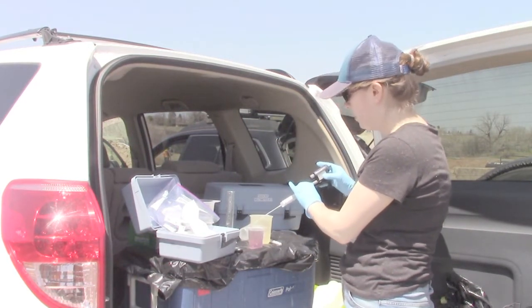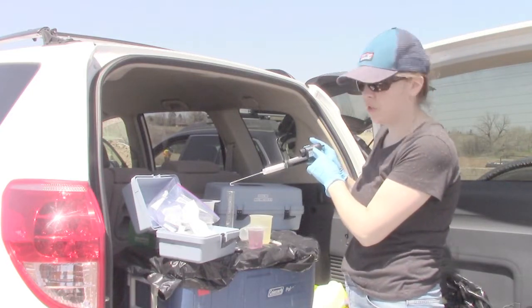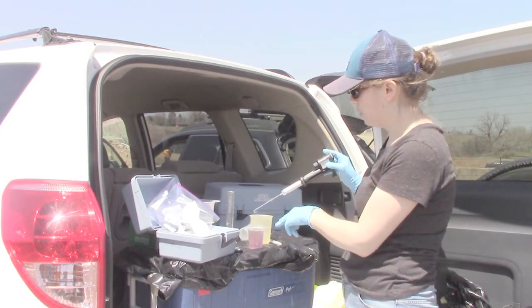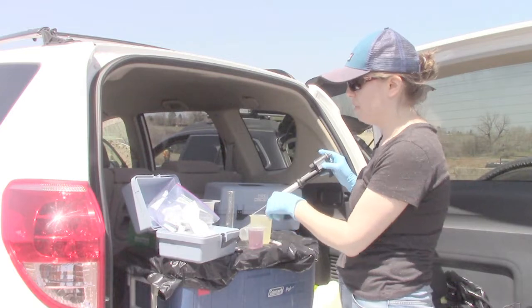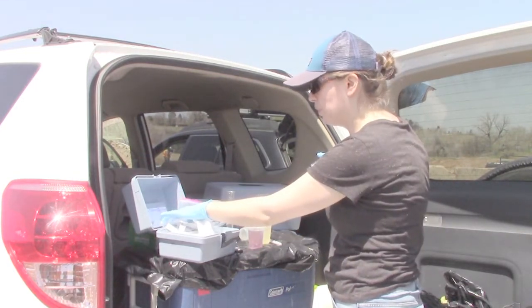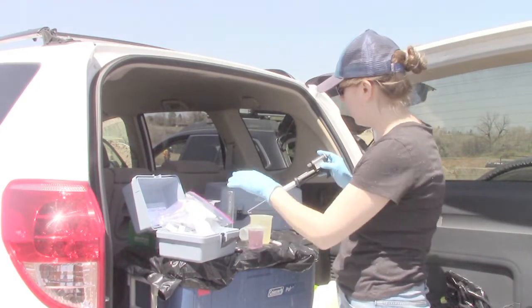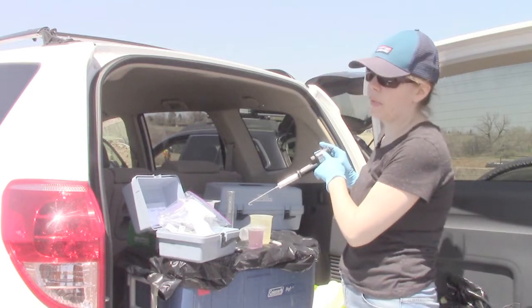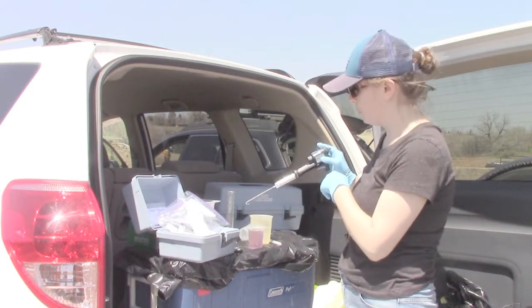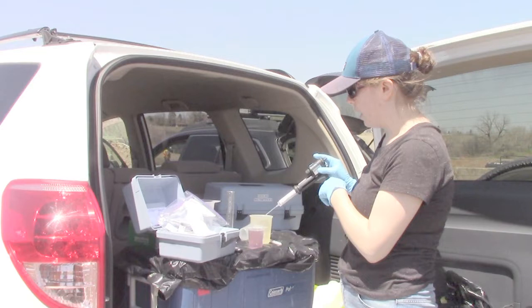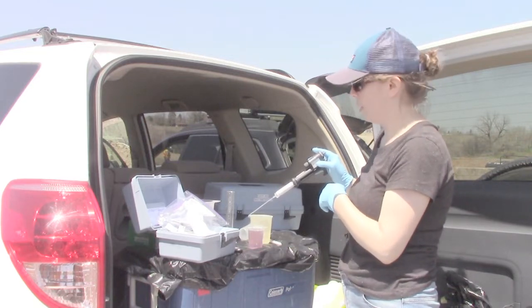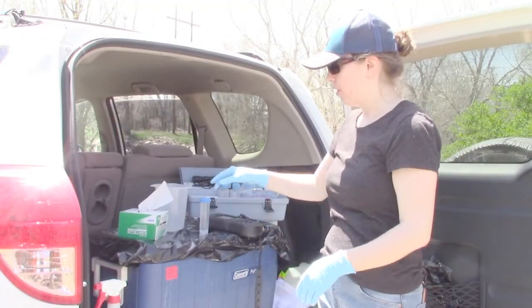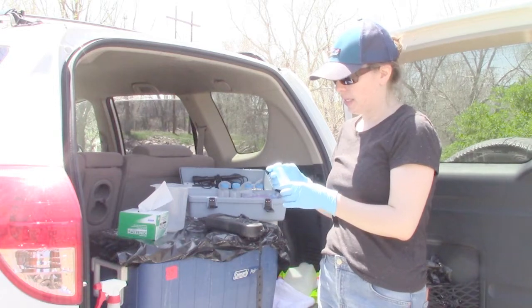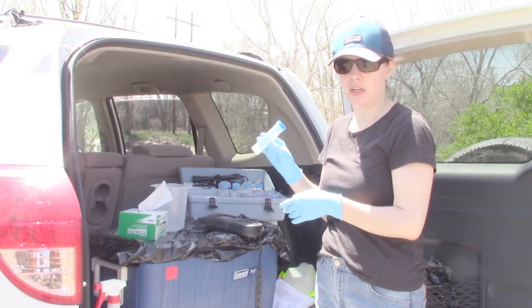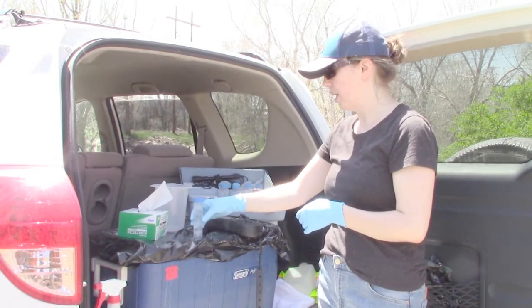So the titrator is saying 229 digits. We have 25 mils of sample volume, and we're going to have a digit multiplier of 0.4. So we're going to adjust that 229 by multiplying it with 0.4 to get the end concentration of calcium carbonate in the sample.